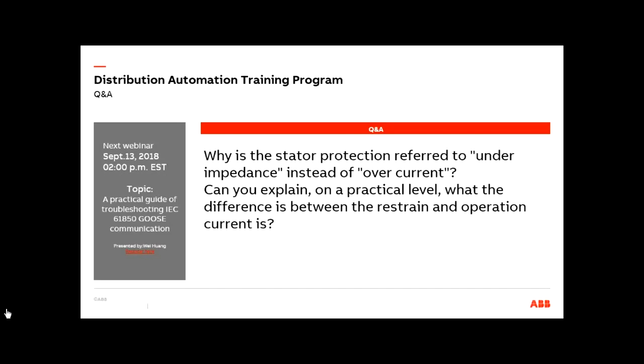And under impedance protection is also a backup protection where we look at the impedance locus movement. In the event of a fault, the impedance locus stays inside the operating area long enough so that we can make the protection operate. Eventually it moves out of the operating zone of the relay, but we will have some time for the protection element to pick up and operate, which is not the case in a normal overcurrent protection.